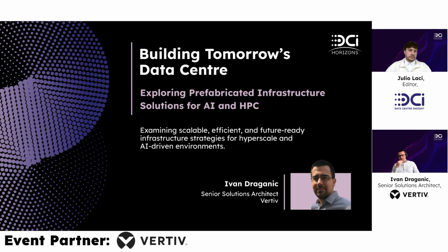I would say the sweet spot for prefabricated elements as such starts at around 5 megawatts, and then expands from there. Anything below 5 megawatts is discussable. Anything below a megawatt, probably just fit it out yourself. But that makes life there's no easier rules - of course, makes sense.